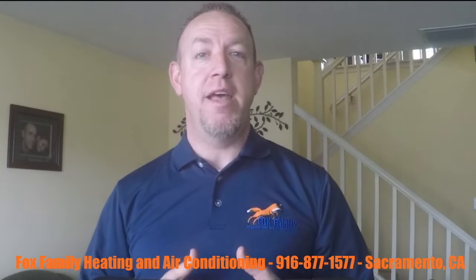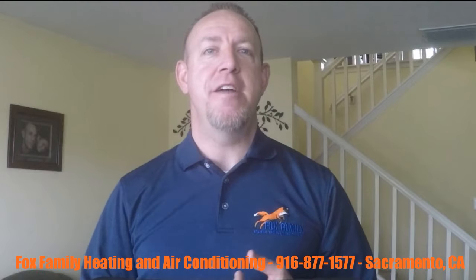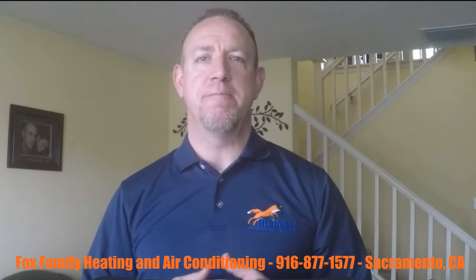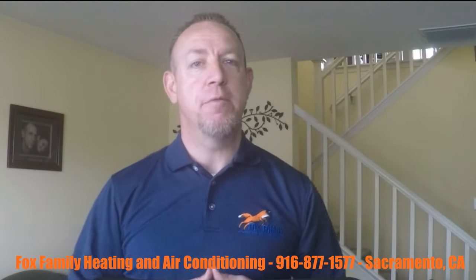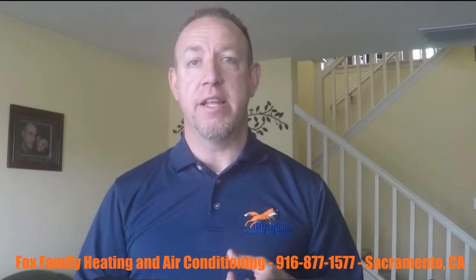Every AC maintenance should take about 45 minutes to an hour and a half. You'll know that we have a structured way of going through your system to make sure that your system is ready to go for the summer months. We start off at your thermostat, checking to make sure that it's mounted securely to the wall and that your batteries are in good condition. We want to make sure that you're comfortable with how to use your thermostat. Some people don't even know how to use their thermostat. Is it programmed to your specific needs? Next, we check all the air filters for size, fit, and cleanliness.